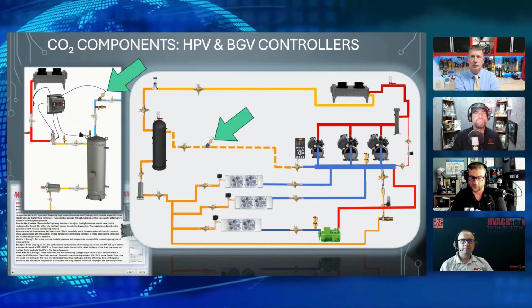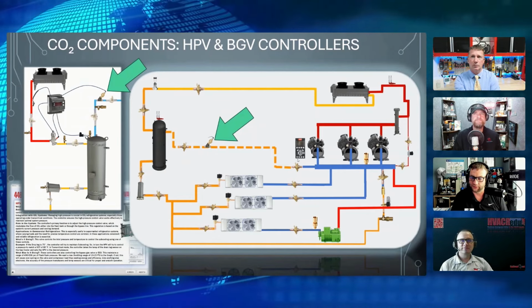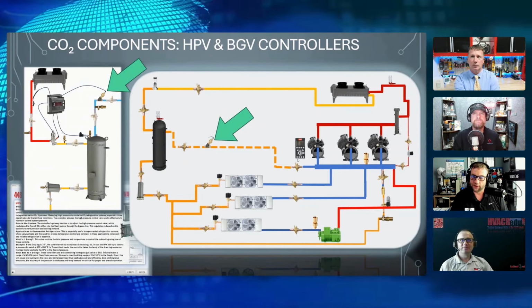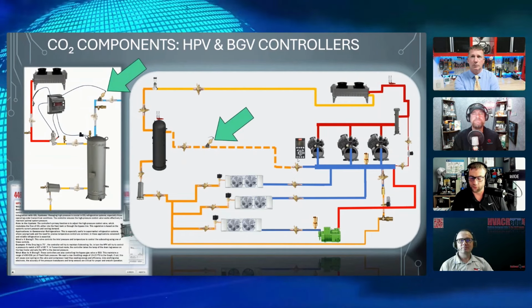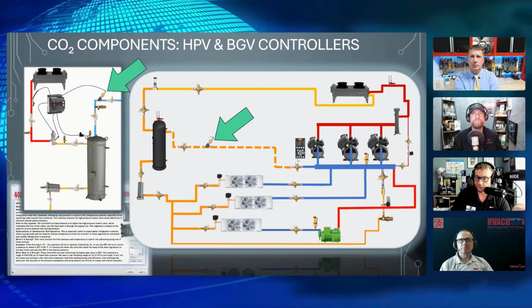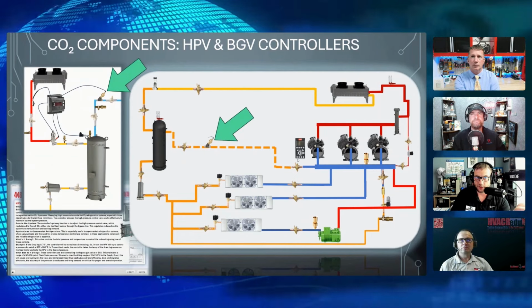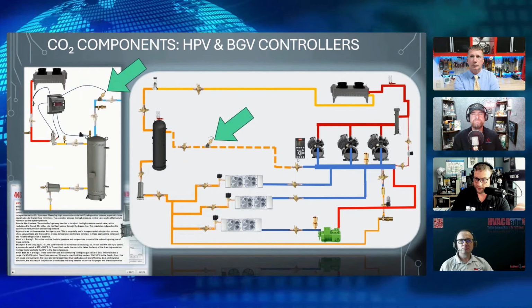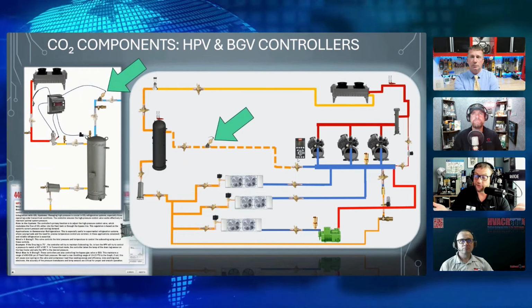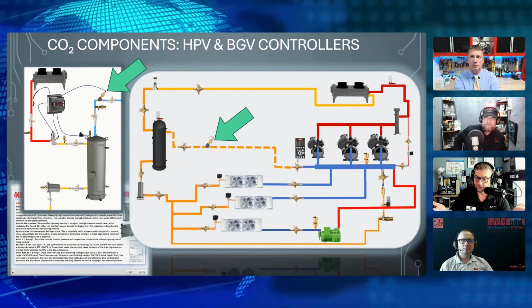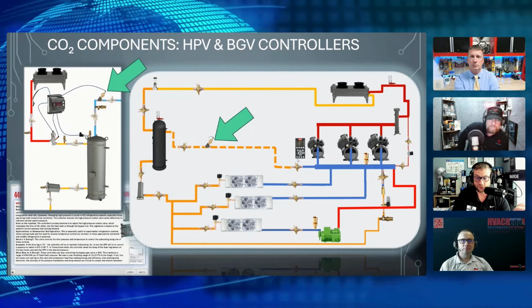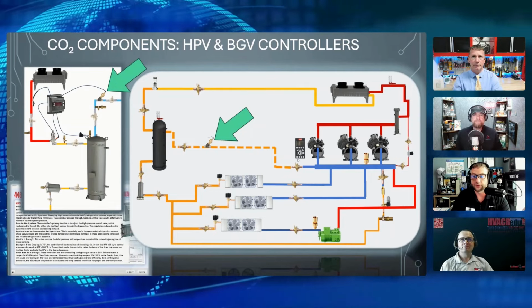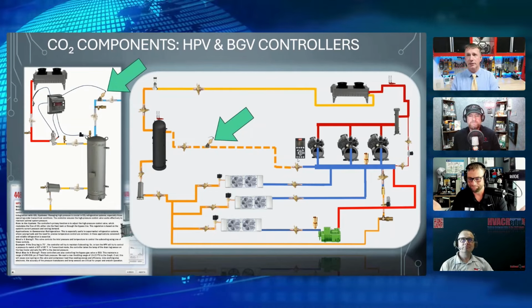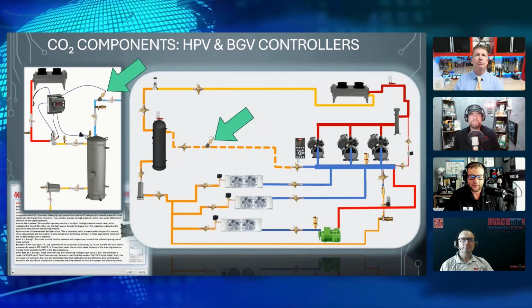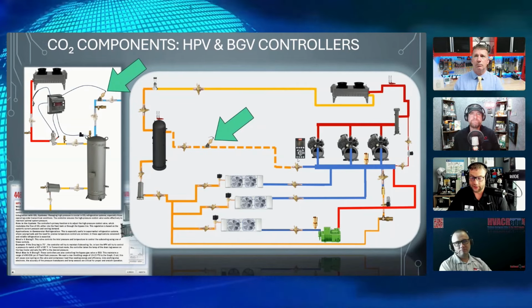Someone else asked me the other day, what happens if you have a shutdown? And I said, well, both valves are going to close down. The reason for that is if you have 1,500 pounds and the gas cooler has a relief of 1740 and the flash tank is supposed to be at 500-some, guess what? If that valve doesn't shut down, the flash tank has a relief of 635. We're going to release the flash tank, start warming up and pressure. Yeah, 100%. So that's why they're interlaced together.